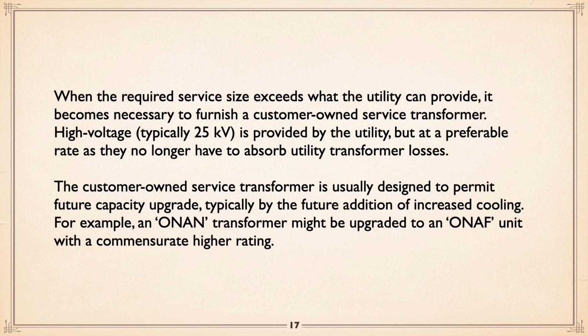Now, so then you're into a customer-owned service transformer. These are usually designed to permit future capacity upgrades, usually by cooling. And you see letters like the transformer will be ONAN. And in the future, you upgrade it to ONAF, which gives you a higher rating of the unit. Now, what do those letters mean?